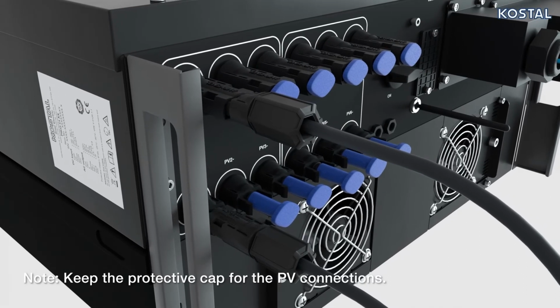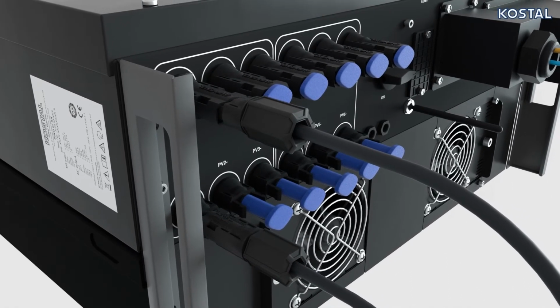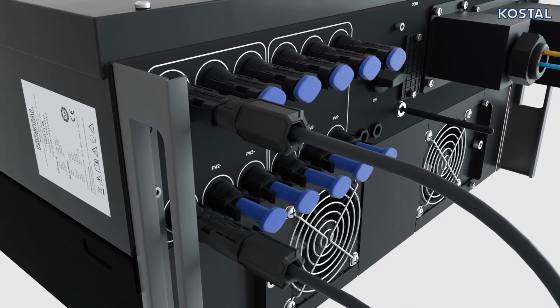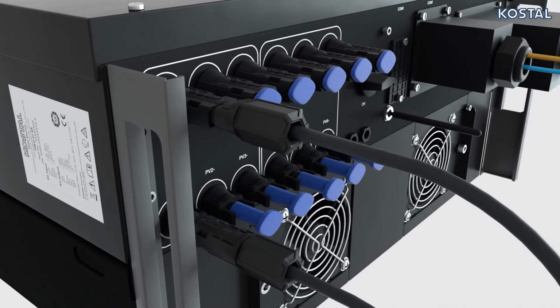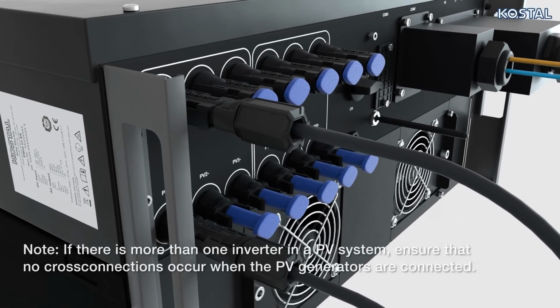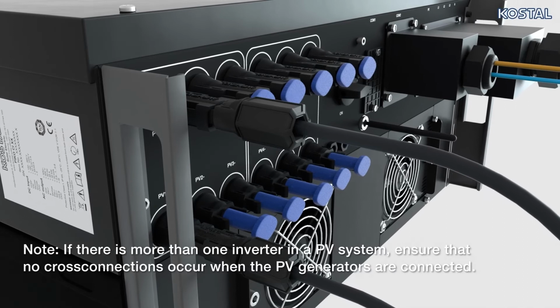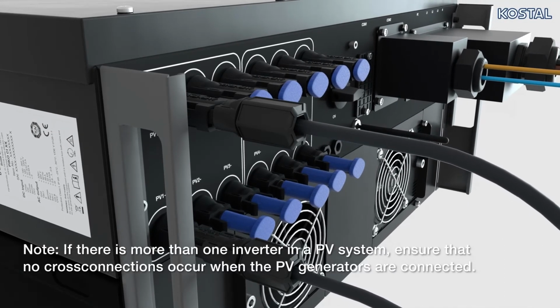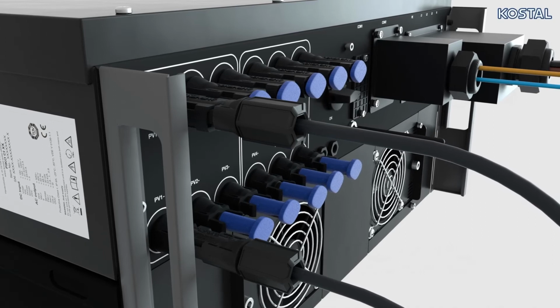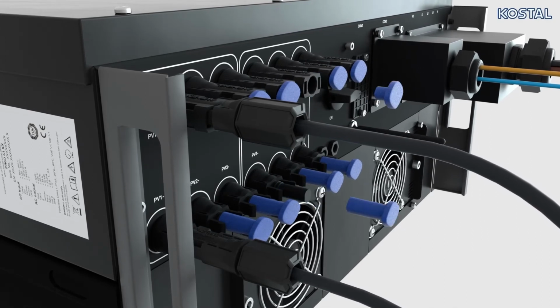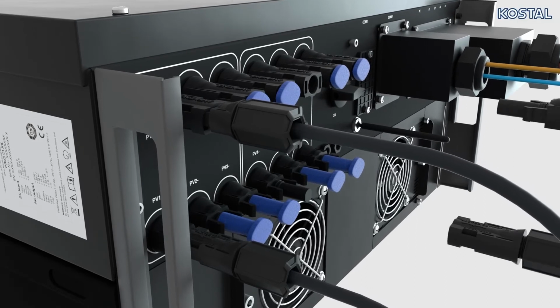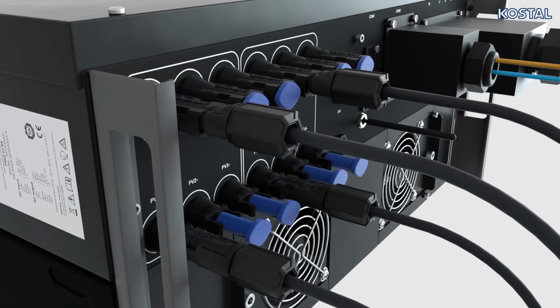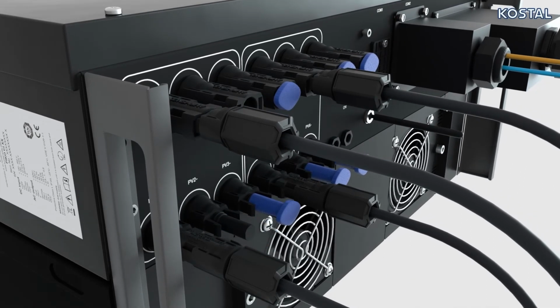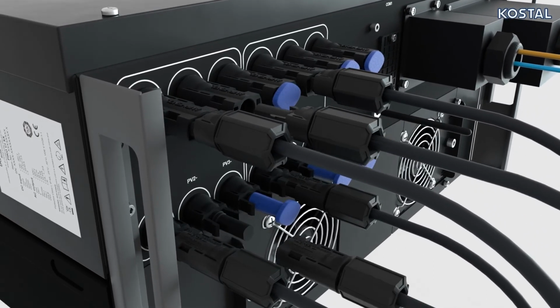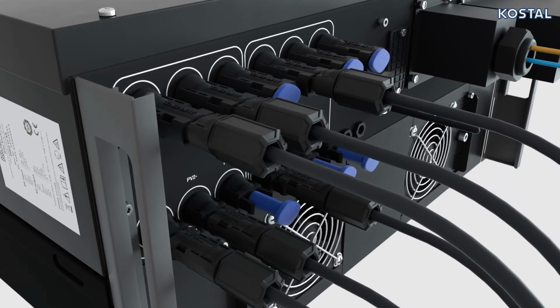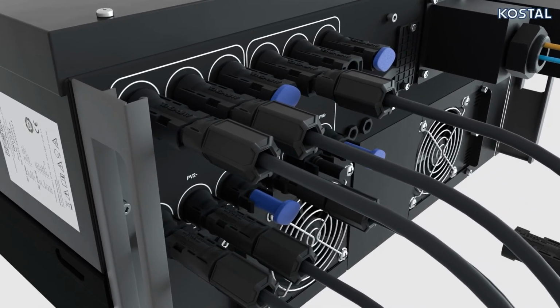The order in which the connectors are connected should follow the white frame and markings on the device. Ensure an even distribution. The inverter has 6 DC inputs. Start with the first 2 PV1 connection sockets and plug the pair of connectors onto the sockets. Connect the second pair of connectors with the 2 PV4 connection sockets in the right-hand connection area. If using more PV modules, start again in the left-hand connection area and connect the pairs of connectors to the PV2 connection socket. Connect the second pair to the PV5 connection socket in the right connector panel.